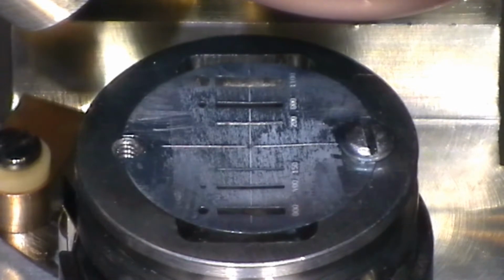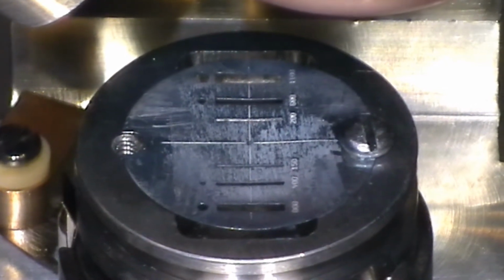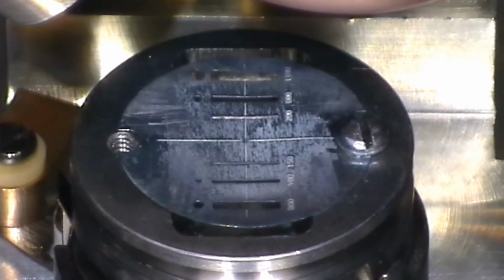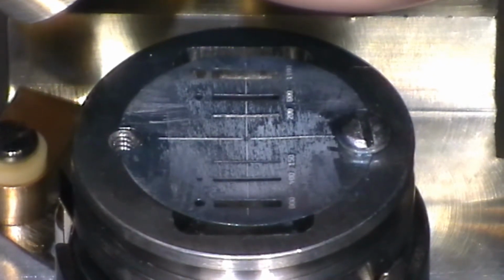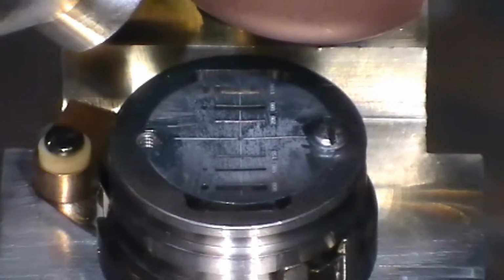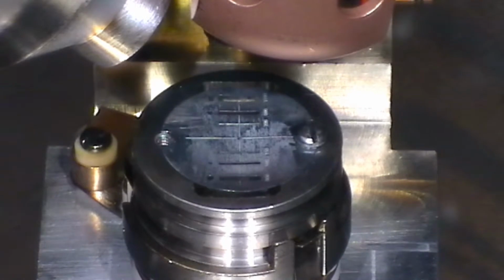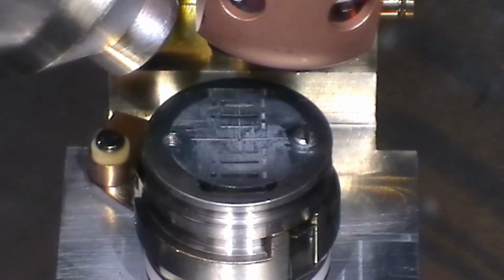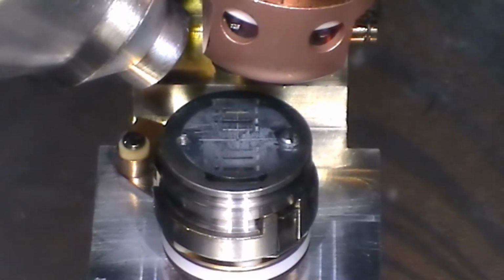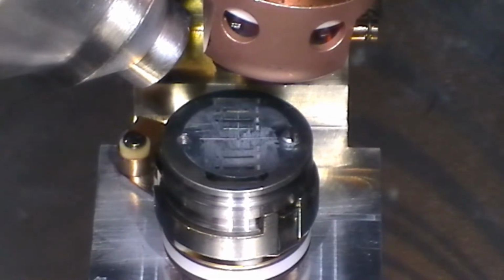We begin by loading the slotted silver specimen into the vacuum chamber. The slotted specimen should be mounted on a recessed sample mount. If you don't have a recessed sample mount, then use some washers or spacers between the slotted specimen and the sample mount. The slits need to be parallel with the nose of the analyzer lens. You position the sample about 0.65 inches from the end of the analyzer lens. This is close to the correct Z position. That's a good starting point.